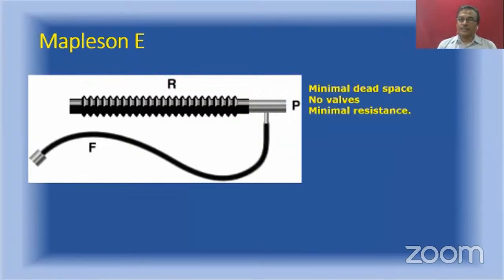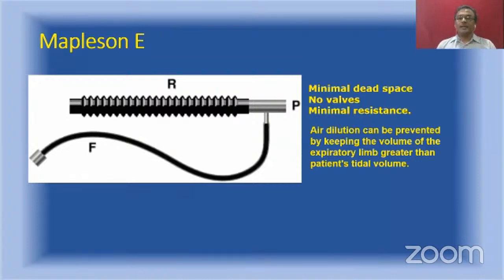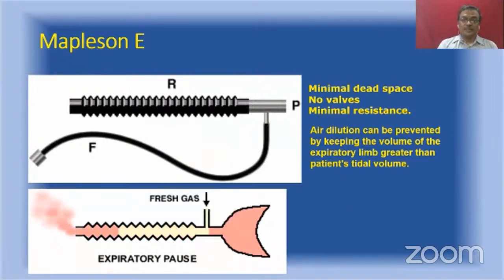And the advantage of Mapleson E is that its dead space is minimum. There is no valve, so it is a valveless circuit. Since there are no valves, the resistance is minimum. So it is a very ideal circuit for infants, neonates. And I said earlier, air dilution can be prevented by keeping the volume of the expiratory limb greater than the patient's tidal volume. And this is how it functions. You can say the fresh gas is continuously reaching the patient end, and during inspiration, the patient draws in the fresh gas as well as gas in the reservoir tube, and during expiration, the expired gas is pushed out by the fresh gas coming from the fresh gas inlet.